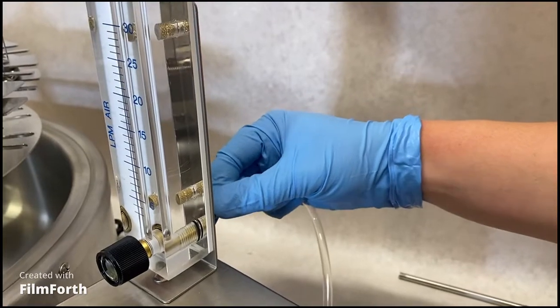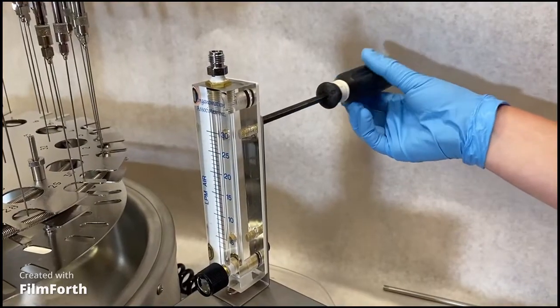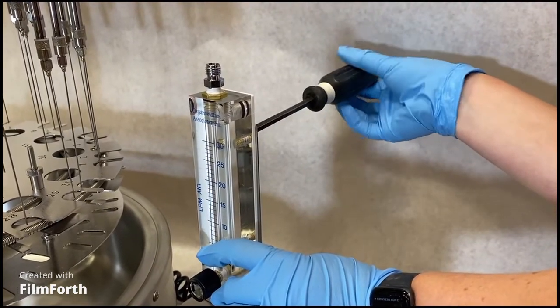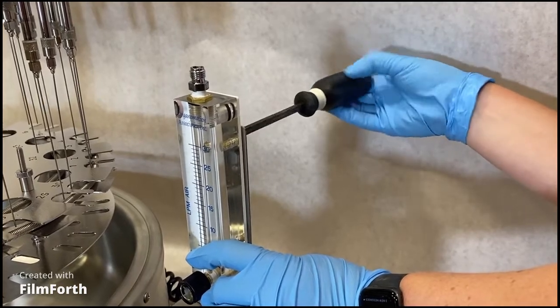If it does not respond, unplug the tube connected to the flow meter and check for gas flow. If there is no gas flow, the meter is likely not the issue. If there is gas flow, check that the ball is not stuck.